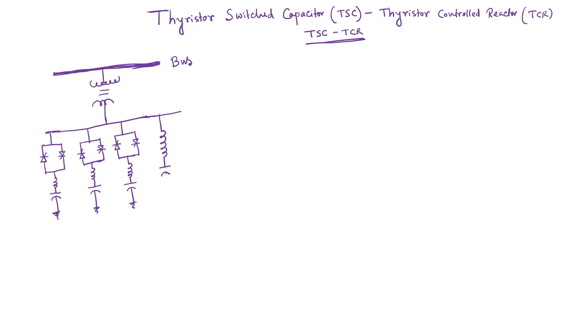This LC filter is required specifically for TCR operation, which I already discussed, and then we will have the TCR unit. This is the bidirectional switch, which we consider as a thyristor, along with the reactor. So here, these are the TSC units, and this is the LC filter to suppress some of the dominant harmonics generated by this TCR unit.